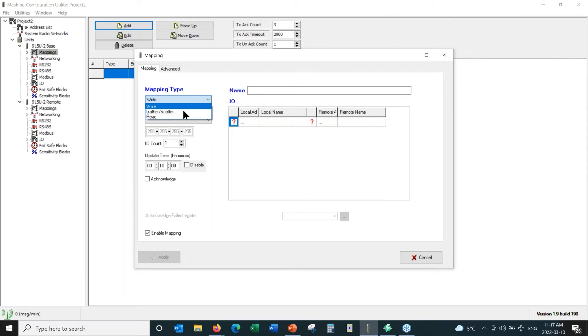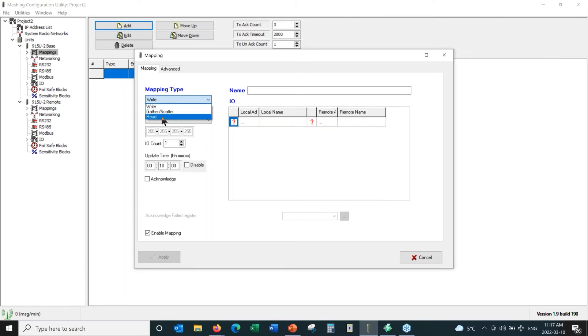There are three types of mappings. A write mapping takes single or consecutive variables of the same type and sends them to the opposite radio. A read mapping pulls variables from the opposite radio — it's the opposite direction of a write. Or we have a gather scatter mapping, which allows you to send several different types of I/O — both analog and digital — in a single transmission.